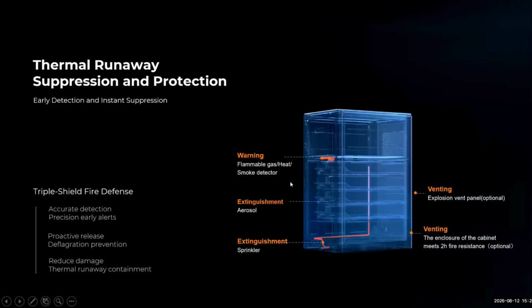Besides the electrical safety design, there is also an internal fire extinguisher as a physical design. We also have fire suppression and protection in the standard configuration: a flammable gas detector, heat detector, and smoke detector. All of these detectors are connected by DIDO signal. When a detector receives any abnormal signal, like flammable gas such as hydrogen, heat of more than 60 degrees, or a higher smoke volume, it will send a signal to the LC, which is a local controller in the BESS cabinet. Then it will send an alarm to the customer.